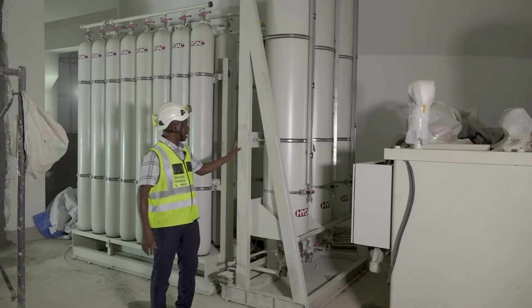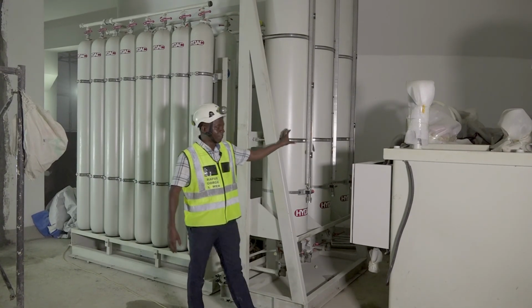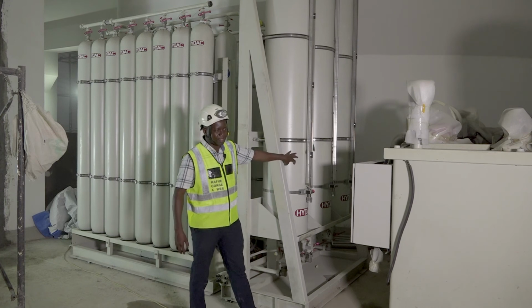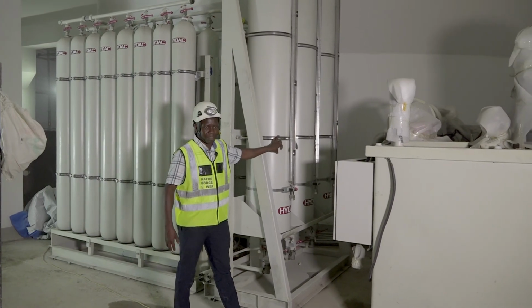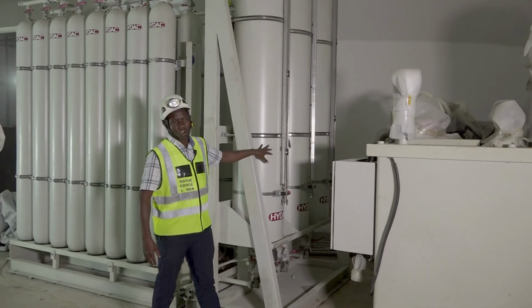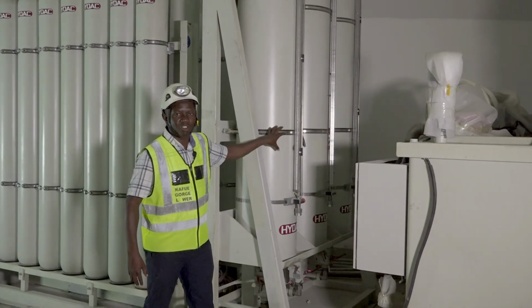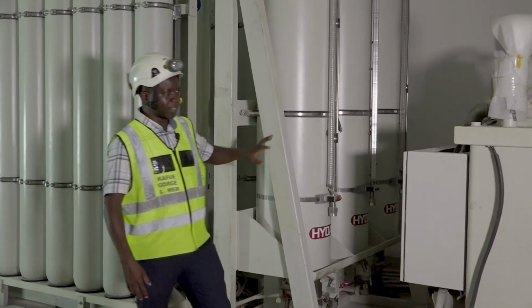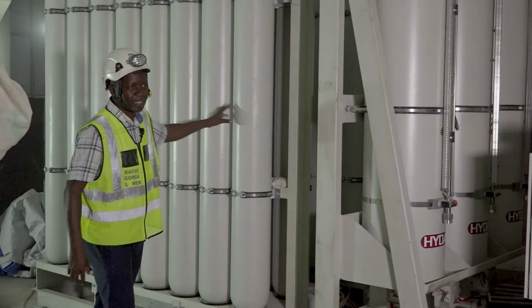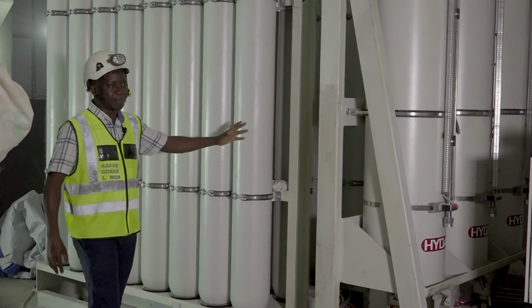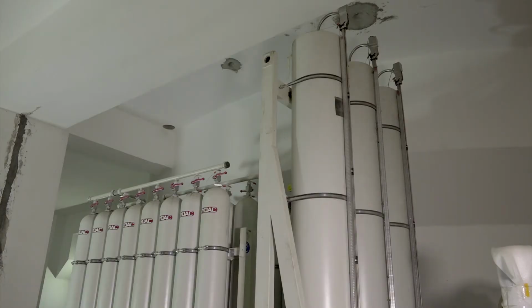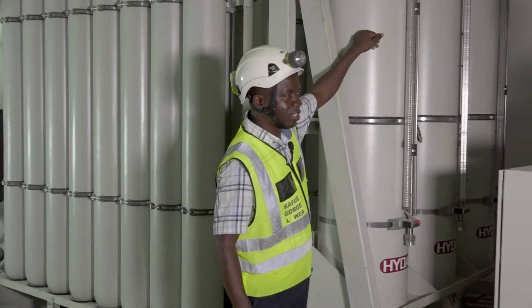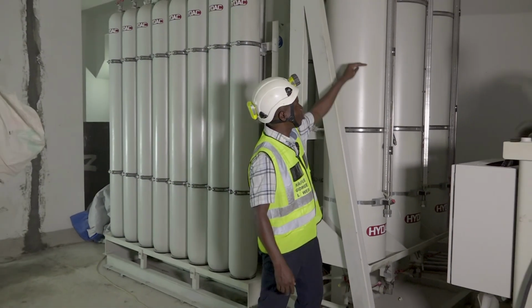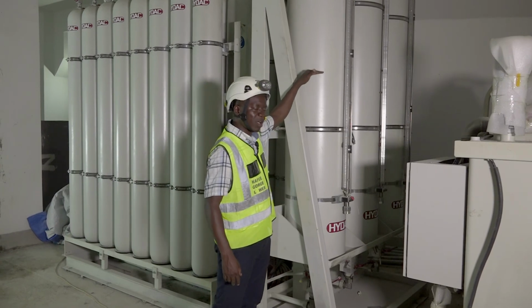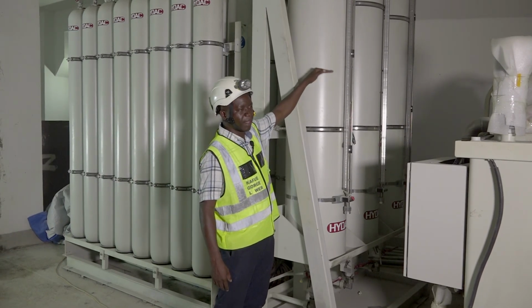So the oil comes into here. This will have a vessel which will have pressurized the oil, 160 bars. At the bottom we'll have oil, at the top we'll have nitrogen. So that nitrogen is coming from these cylinders here. So this is a nitrogen bank. Depending on the requirement here, we'll either push in nitrogen from the top or push in oil to maintain the required level of oil in this vessel.